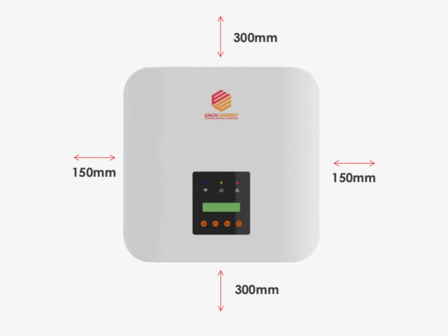While ensuring installation conditions, the smaller the inverter, the shorter the peripheral distance requirements. Take EACH Energy for example. Only 150 mm is needed on the left and right sides of the inverters, which of course means heat dissipation is better and the same area can install more machines. Because it's installed outdoors, the protection level of the inverter must reach IP65 or even IP66, which can prevent dust, rain, and corrosion, and adapt to harsh external environments.